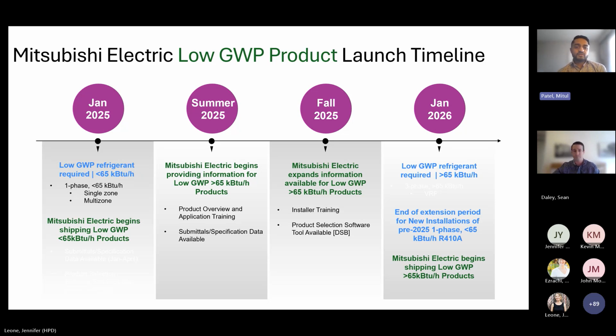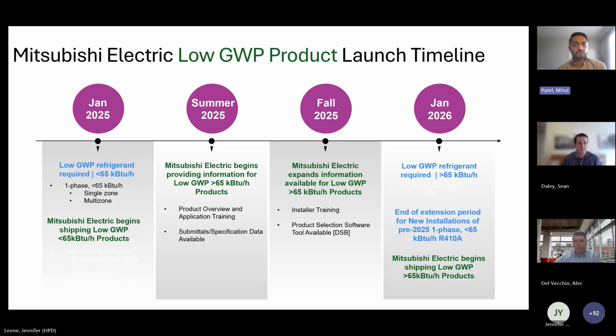As we developed products to transition to low GWP refrigerants at Mitsubishi, we used the schedule provided by the AIM Act, including the 1-year extended period for new installations, to completely redesign about 500 SKUs. Our objective wasn't just to change to a new refrigerant, but to deliver even higher efficiency with improved heating performance at low ambient temperatures, and to make products easier to install and service while maintaining the reliability and flexibility building owners and engineers expect, especially when utilizing A2L refrigerants.